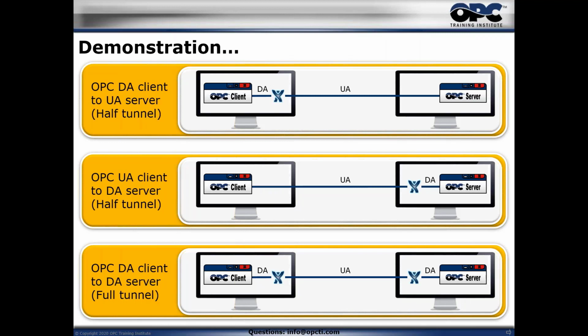Yes, so the point is, with this one here, or this one here, you can connect to not just one OPC server, but two OPC servers. So you can actually connect over here, to this one, and to this one, if you will. If the primary fails, you will automatically move over to the standby, and that's already built into the tunnel.